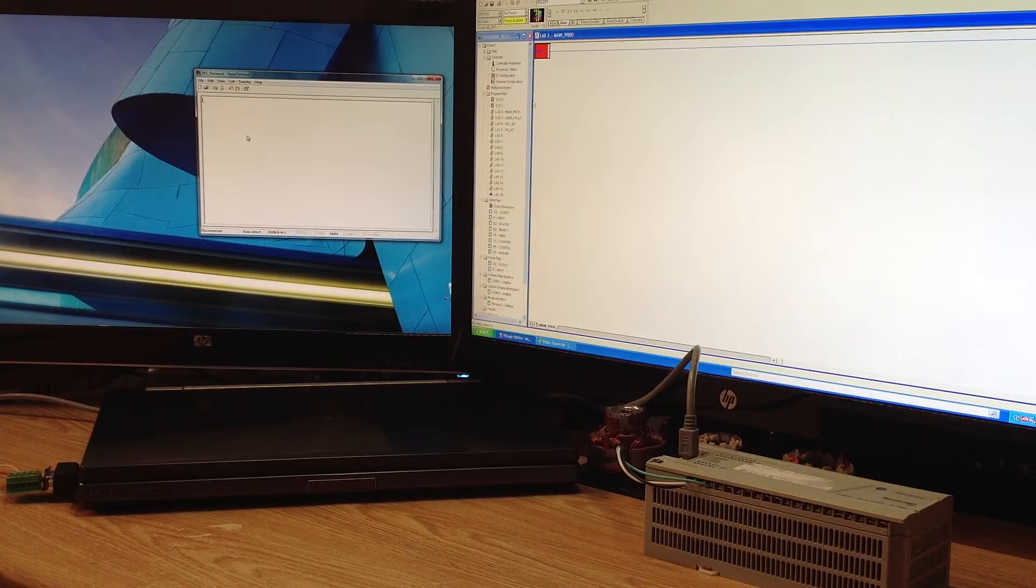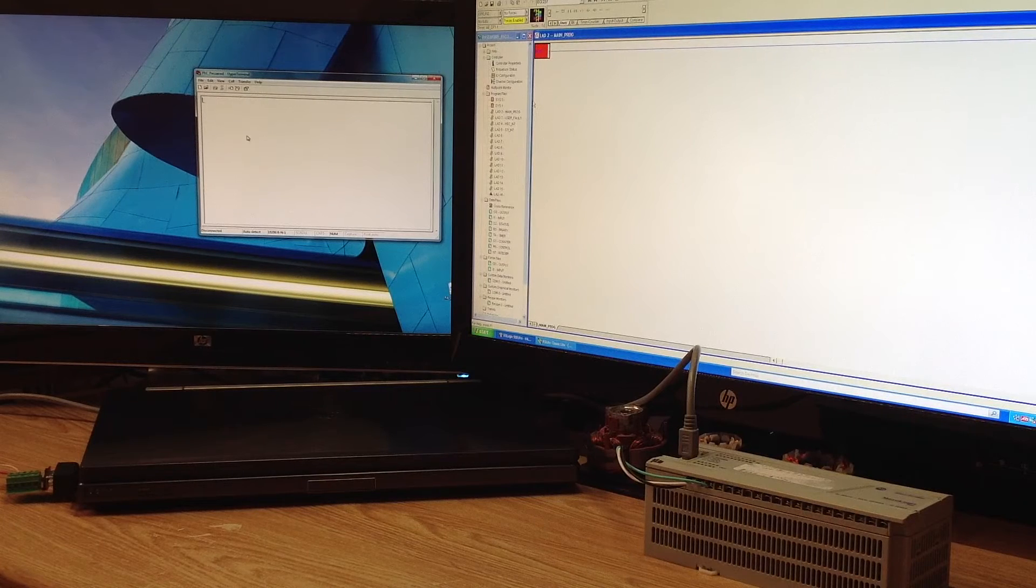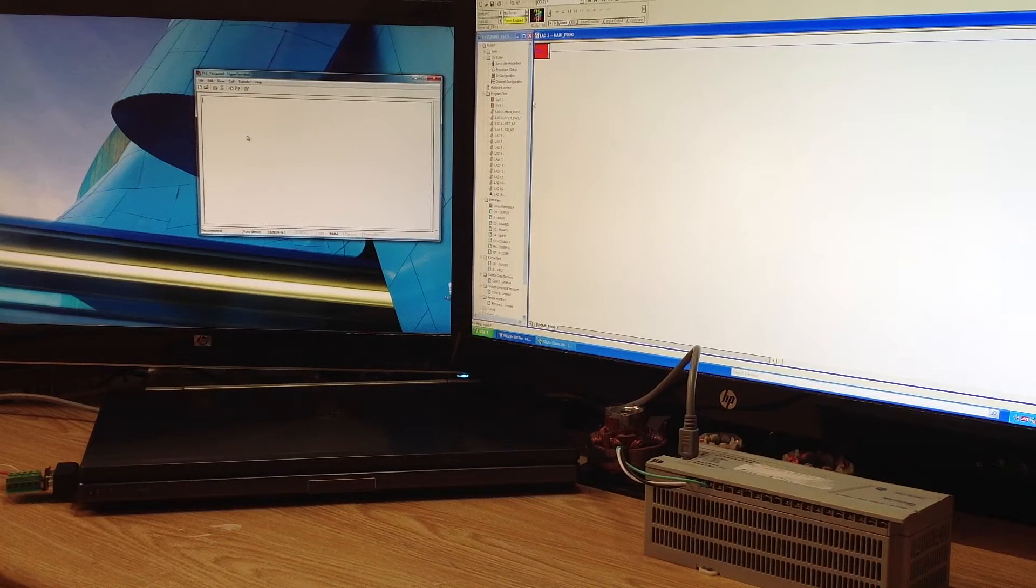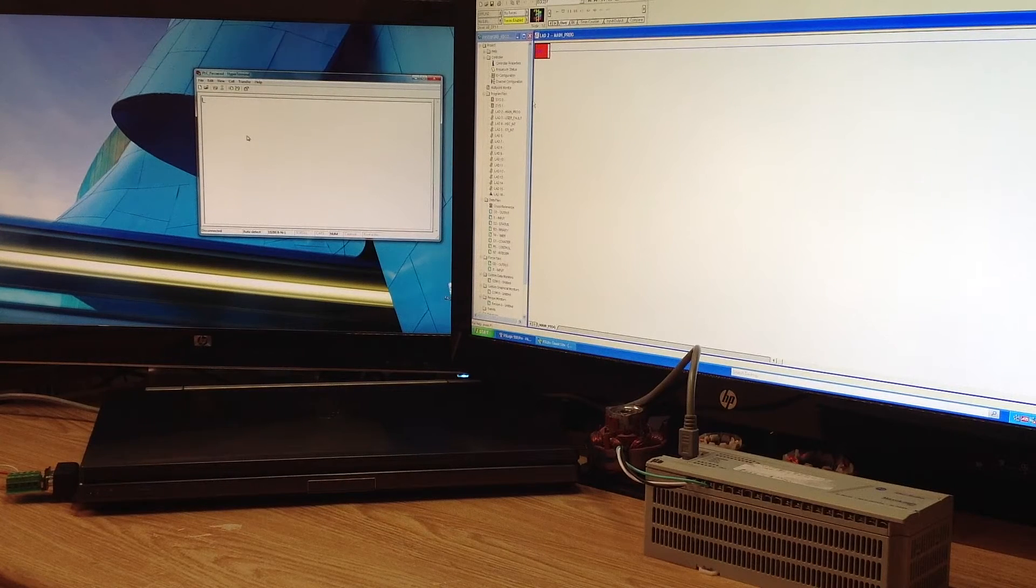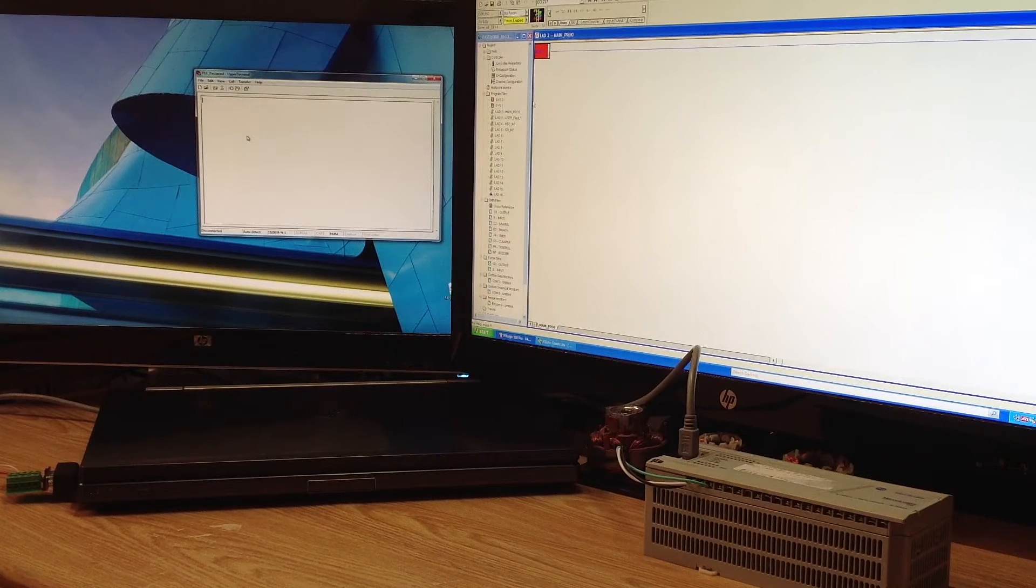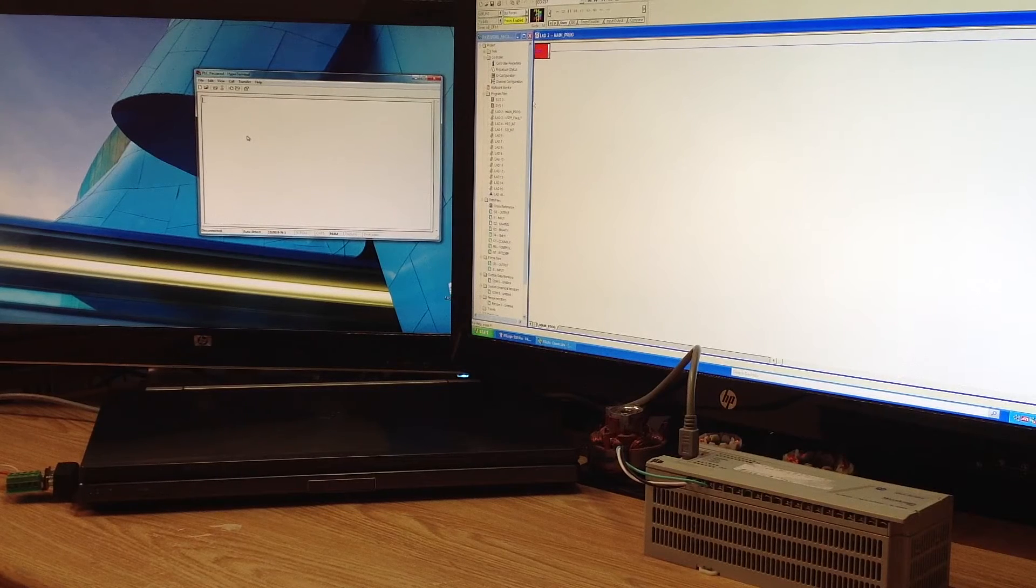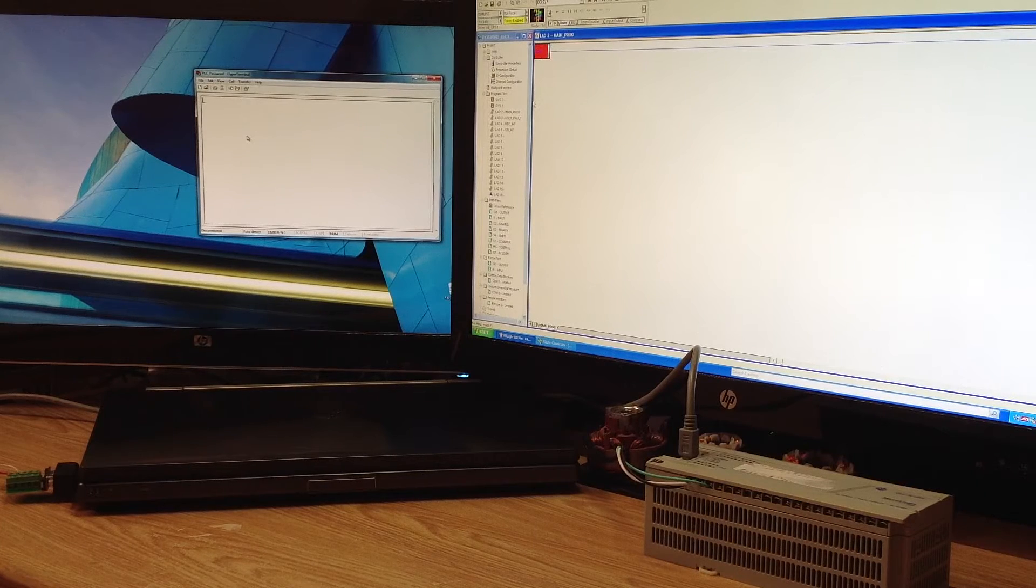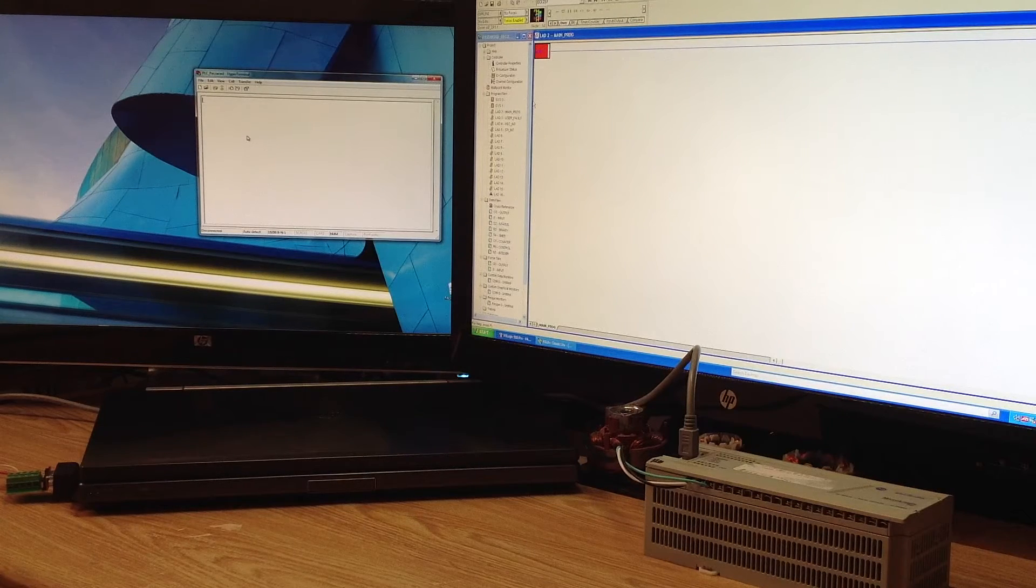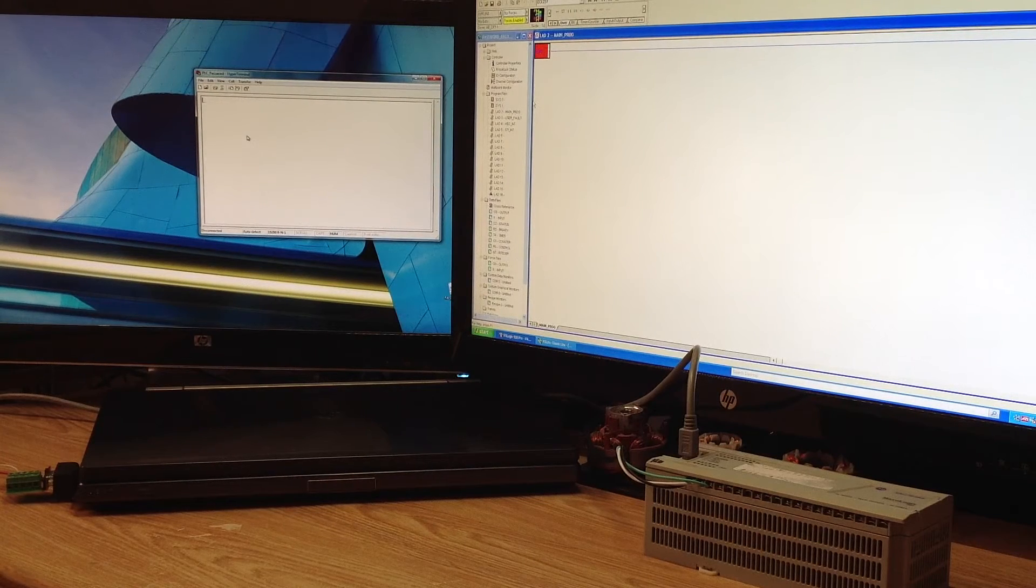After today, I'll make up an official cable so I can do this if the situation ever arises, but it's pretty simple. All I have set up here is a standard serial cable from the programming computer to the PLC. Then off that cable, I have another cable plugged into a second serial port, and I'm tying two and five on the programming PC to two and five on my second PC with the laptop on the bench here.